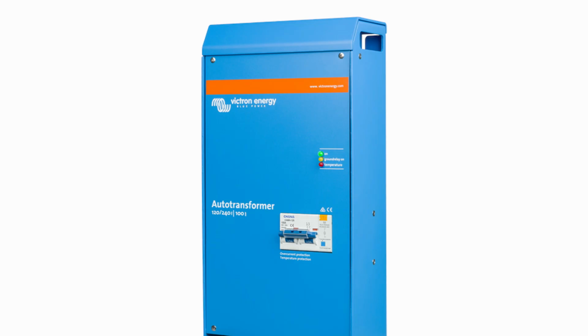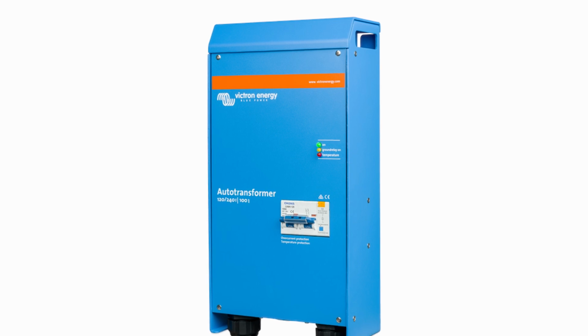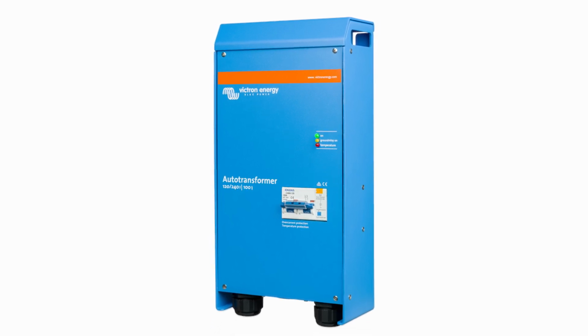Victron Autotransformers can be used in a wide range of applications. We can use it to step up from 120 to 240. We can step down, so from 240 to 120 volts. We can use it for neutral forming, so take 240 volts and get 120, 240 output for 120 volt loads. And we can also use it to balance loads if we have an imbalance from L1 to L2. The Victron Autotransformer has the ability to create a neutral to ground bond that is controlled by the inverter for certain applications.